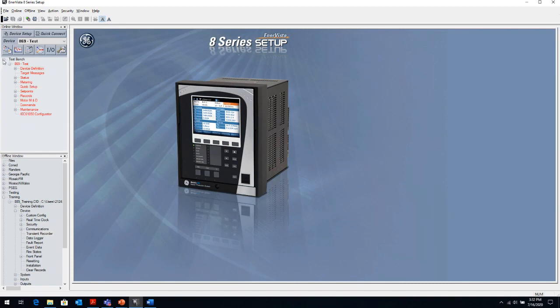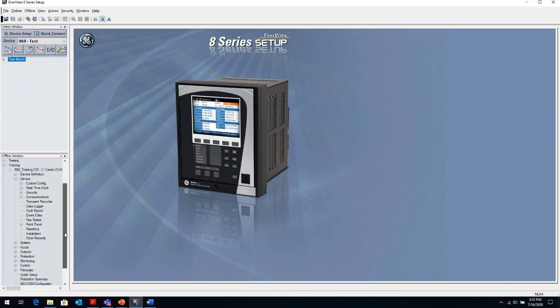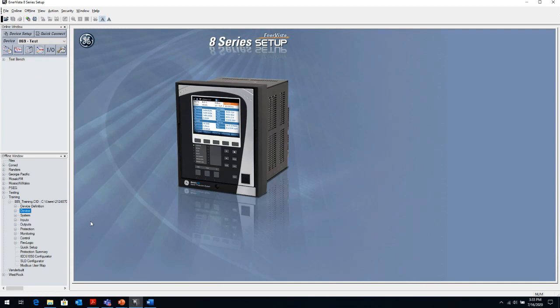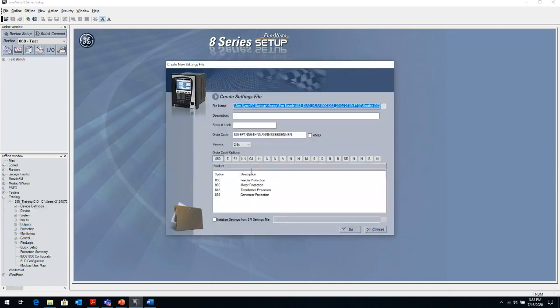So let's go into the offline window. The offline window is basically where, as maybe a protection engineer, you would create settings, or look at the settings that were downloaded from a relay. The way you would create a setting is you would right click on any of the three items and click on new setting file, and you just create a model number based on the relay that you've purchased or installed, and match up the model number to that relay. Every option is available for you to select, so you know exactly what those numbers mean in the model number.